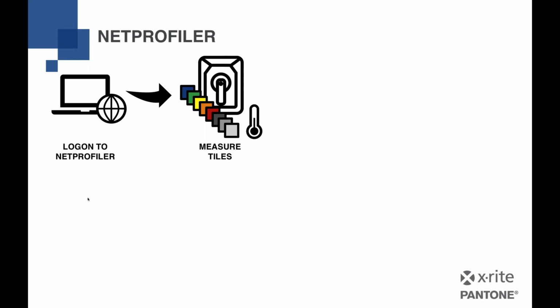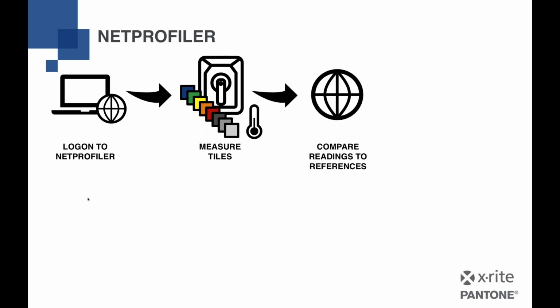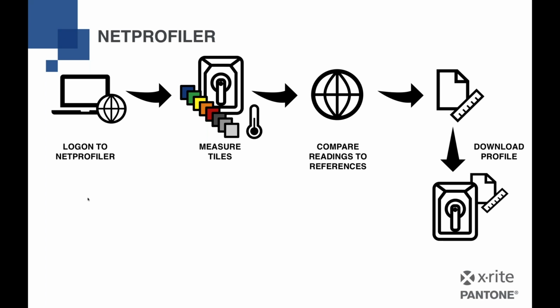The tiles are actually manufactured and certified, or equipped with reference values, on the same equipment we use to produce and calibrate our instruments. So they're fully temperature controlled. Then these readings are, of course, taken with the temperature of the environment you are performing these measurements in taken into consideration, because ceramic tiles are thermochromatic. They change their color behavior with temperature changes, but it's a linear effect which you can nicely compensate for. So once the readings are compared to the references stored on the server, a profile might be generated, and that profile might be downloaded to the instrument to compensate for minor variations.